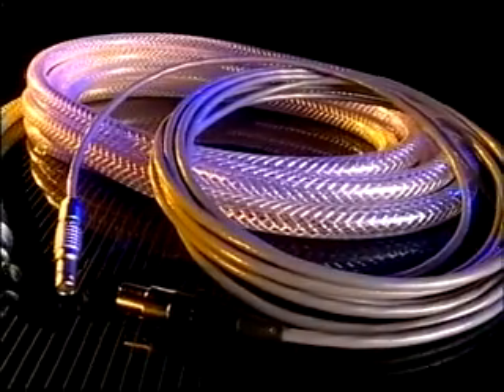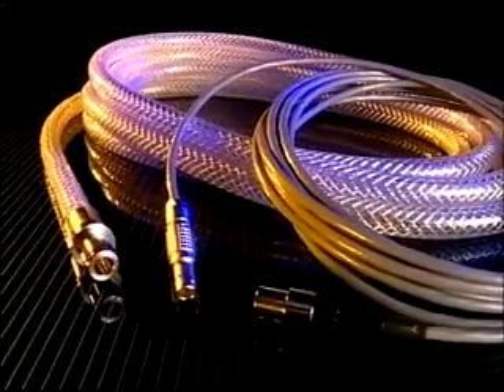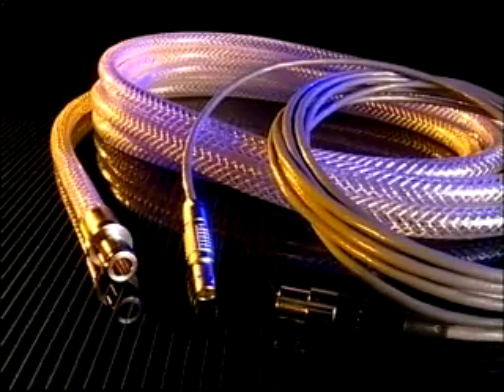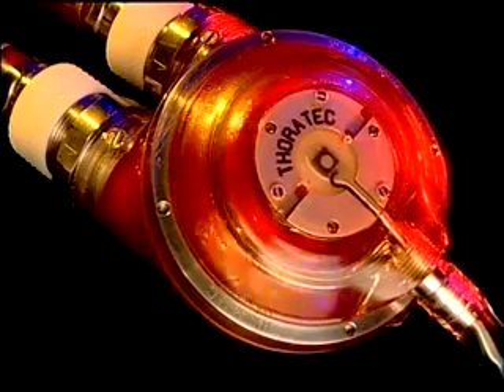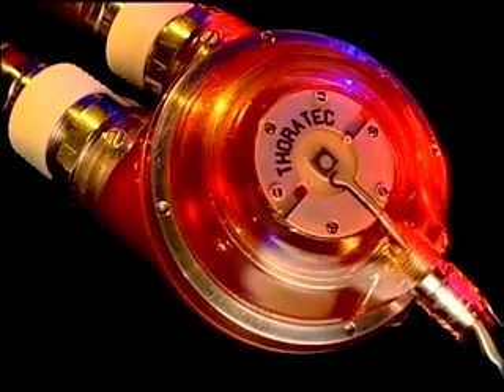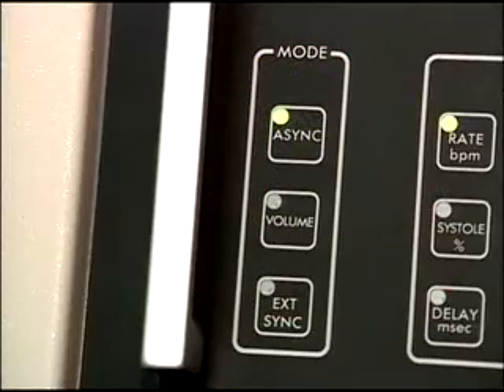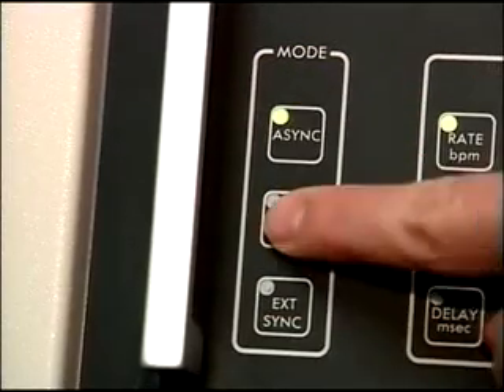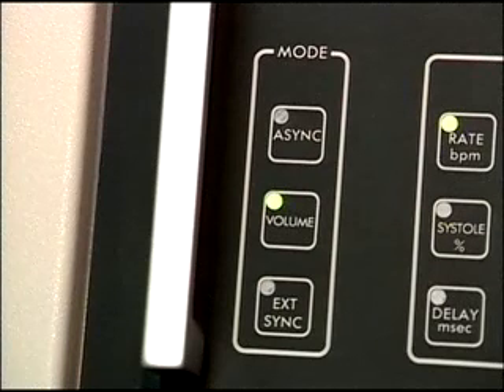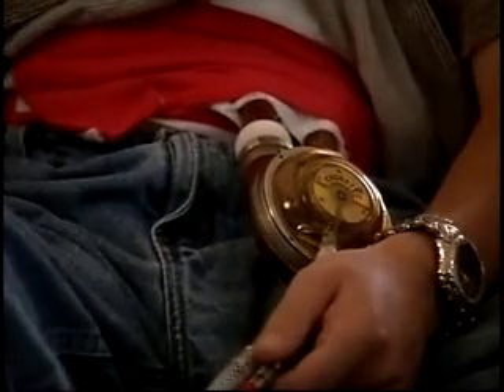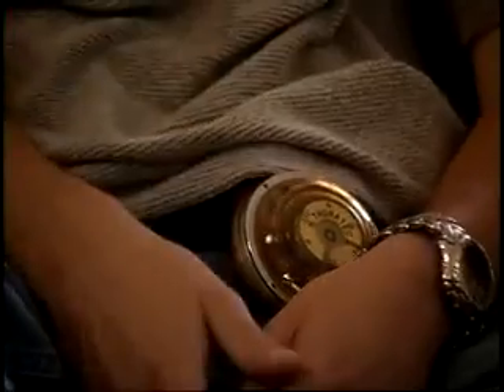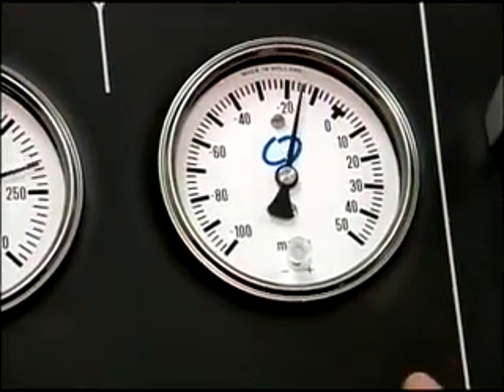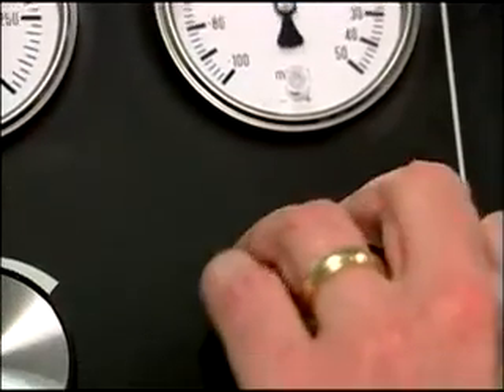The console is connected to each VAD pump by a pneumatic lead and an electrical lead, which regulates and monitors the system's operation. Each VAD fills and empties in cycles, driven by air pressure and vacuum from the console. The console operates in one of three modes: asynchronous, volume, and EKG synchronous. The normal mode of console operation is volume, also known as full to empty, where the VAD rate changes automatically based on cardiac preload. During each fill cycle, the drive console creates a vacuum to help fill the blood pump. The regulator control knob below the vacuum gauge can be used to adjust the level of vacuum.